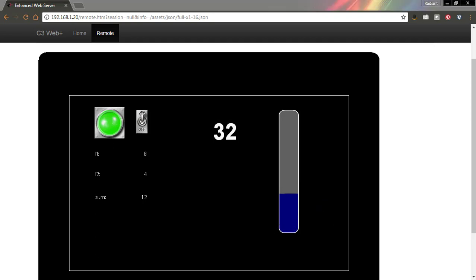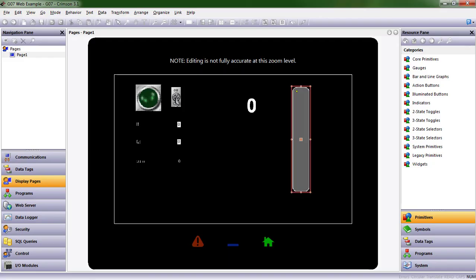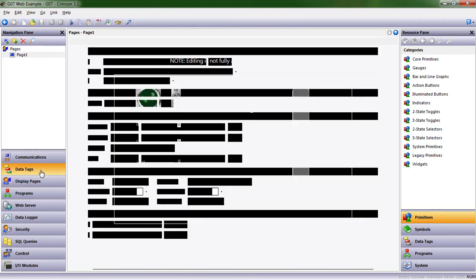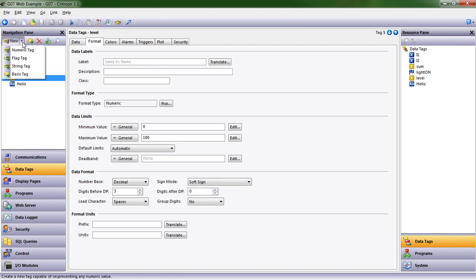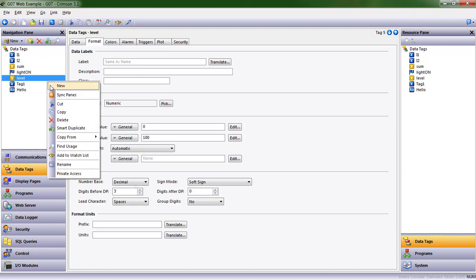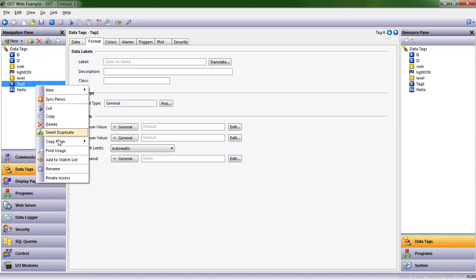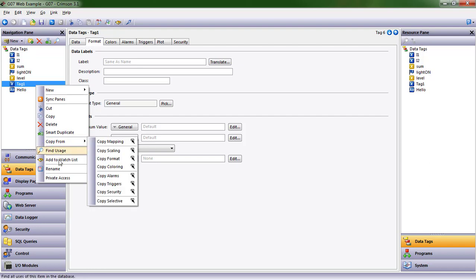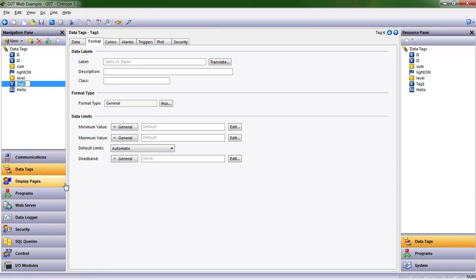So let's go into our database in Crimson 3.1. Here it is, and the first thing we need to do is create that set point. We're going to create a numeric data tag. Let's rename that. I'm hitting F2. You can also right-click and choose rename, and let's just call it set point so it's real clear to us what this is.